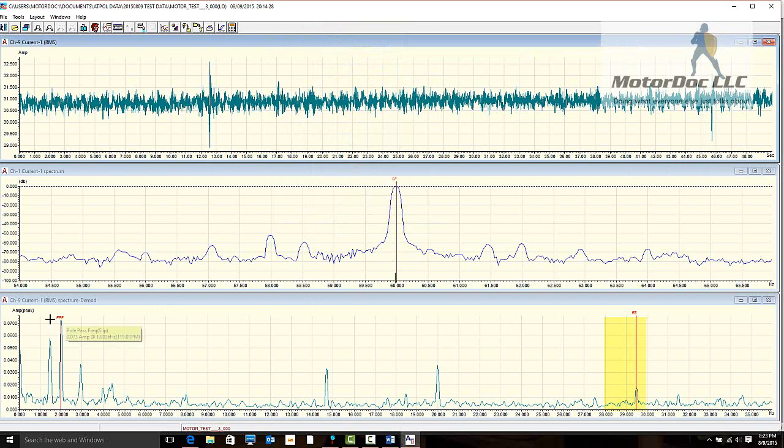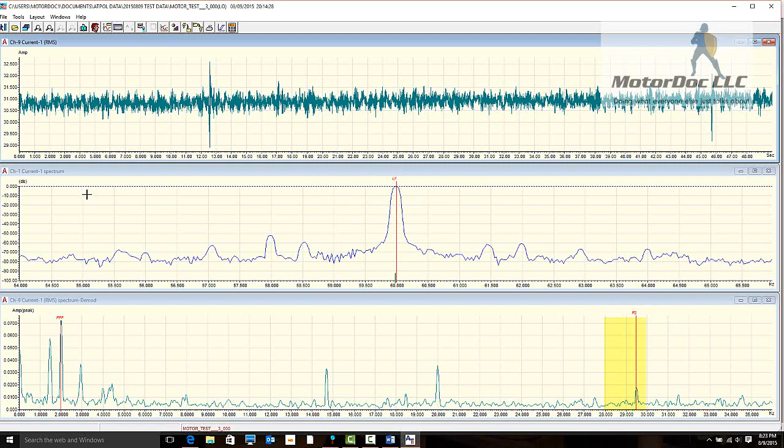There's our pole pass frequency peaks. There's our running speed which is 1768 RPM. It is a 1765 RPM motor. That is about what's expected. Line frequency is really close to 60 hertz. So with this, I hope you've enjoyed your quick tour. Let's take a look at the high frequency data real quick. I want to see that static eccentricity.